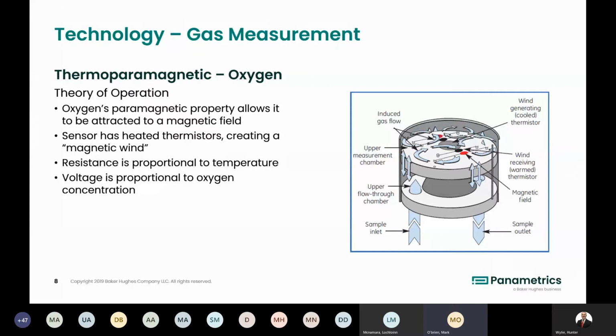Now, as this wind transits across certain thermistors, the electrical properties of those thermistors will change. They cool or don't cool depending on how much oxygen is there. So then we can convert the change in resistance of those thermistors and correlate the change of resistance to the presence of oxygen. So we have an electrical output from a transmitter based on the oxygen presence. So the XMO2 works on this. It has a very robust EXD package or weatherproof package where required. It's quite compact and can be located in almost any environment, hazardous area or not. So if we just move on there, yeah.